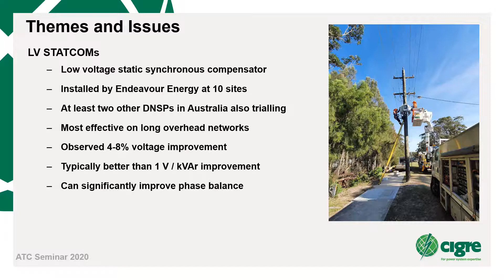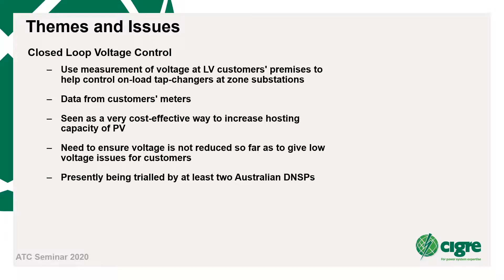Another method of managing voltage in LV networks, although across a much wider area, that has been trialled by at least 2 utilities in Australia, is closed loop voltage control. This is the use of the measured voltage at LV customers' premises, obtained from real-time meter data, to control the set point of on-load tap changers at zone substations. This has the potential to be a very cost-effective way of managing voltage and thus increasing DER hosting capacity of networks.